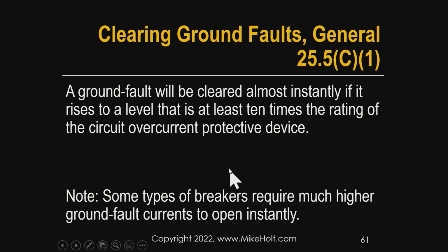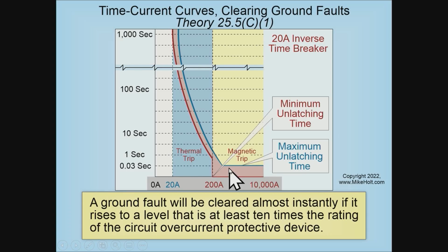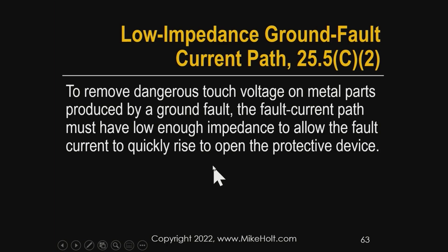Clearing ground faults. Well, a ground fault is the same thing as a short circuit, and we mentioned in the graphic here 10 times, which we can't say. So for a ground fault value, if you got to the instantaneous, it's going to trip it very, very quickly. And then, of course, thermal, longer time. All right? Low impedance ground fault current path. To remove dangerous touch voltage on metal parts produced by a ground fault, the fault current path must have sufficiently low impedance, not resistance, because we're in alternating current circuits, to allow the fault current to quickly rise to open the protective device.